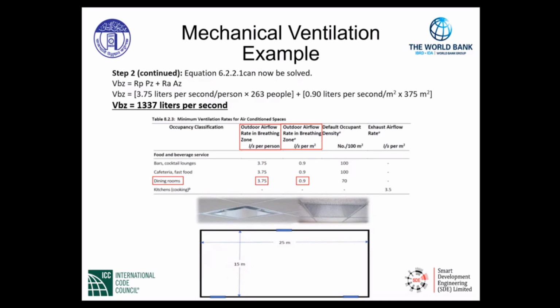We integrate these particular values in this equation, and as can be seen here, V sub BZ equals the quantity 3.75 liters per second per person, times, remember our population of our zone, 263 people. We take the product of that portion of the equation and add it to the following portion of our equation, the area portion, 0.90 liters per second per square meter, times the area of our dining room, 375 square meters. Therefore, V sub BZ equals 1,337 liters per second.